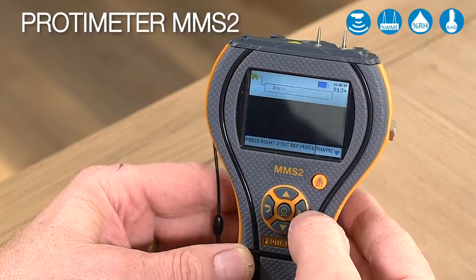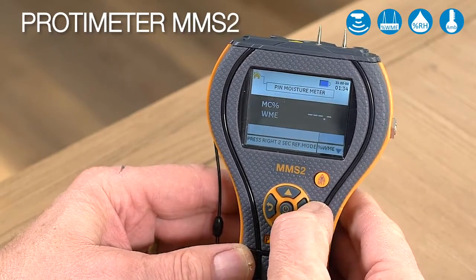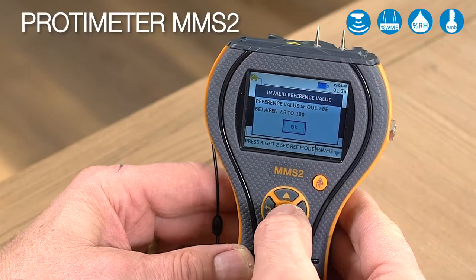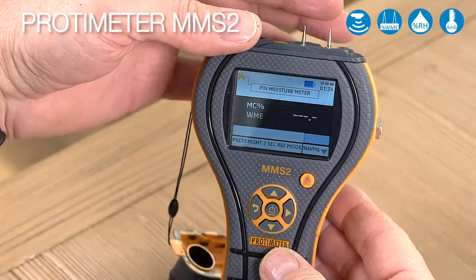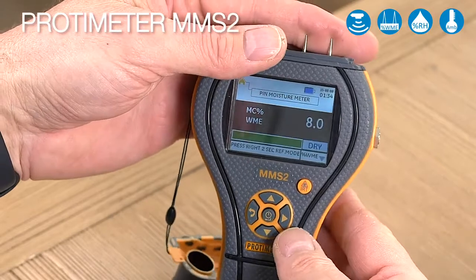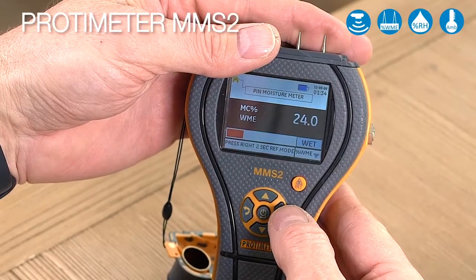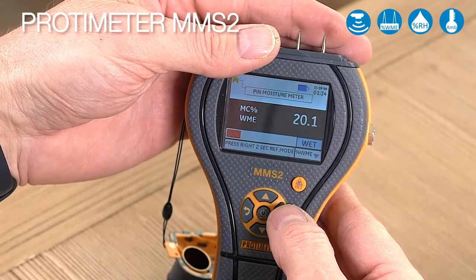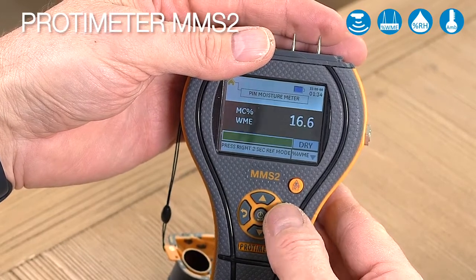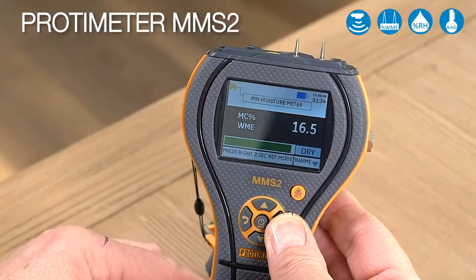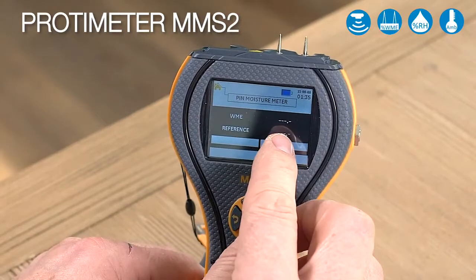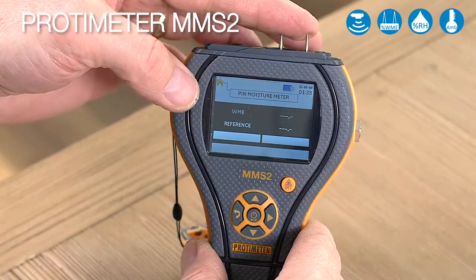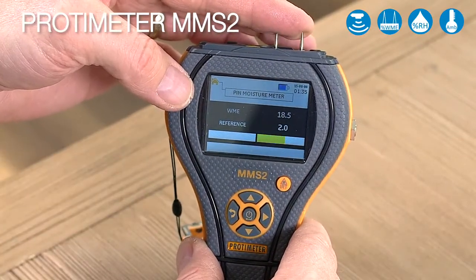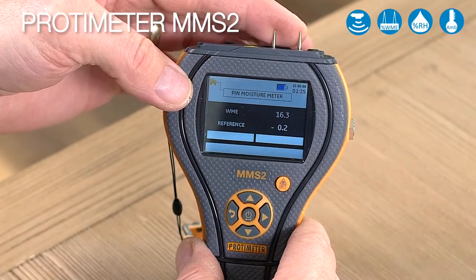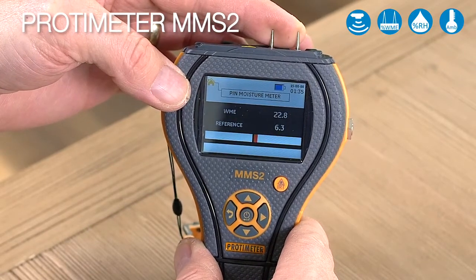If you go into pin mode and press the right hand button for 2 seconds, you can get a reference value, meaning you can take a dry standard. Let's take a measurement here and call our dry standard 16.5%. Hold the right hand button, and now on the top display you'll see the actual reading. On the lower display, you'll see whether you're above or below that dry standard you stored by pushing the right hand button.